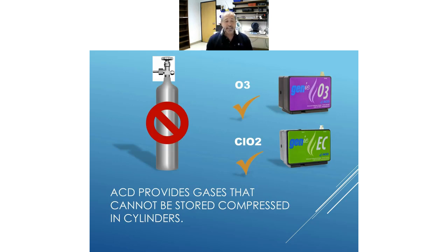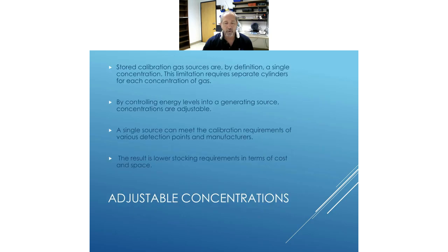So again, we provide gases that can't be stored in compressed gas cylinders, like ozone and ClO2, which is how we shorthand refer to chlorine dioxide, by the way. As I referred to earlier, a stored calibration gas in a cylinder is going to be exactly what you order. You've got to get X ppm, 25 ppm, 10 parts per million, whatever. And that's what's in that gas cylinder until it starts reacting.